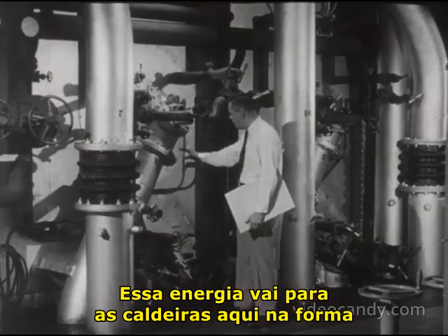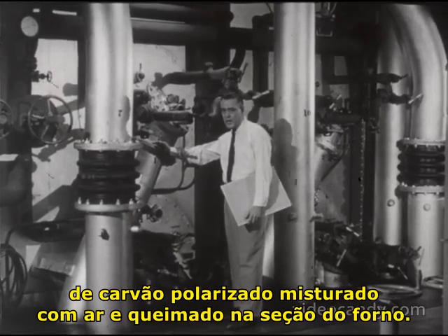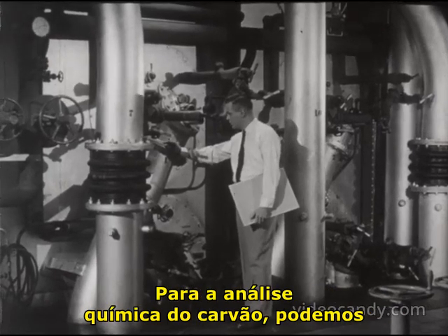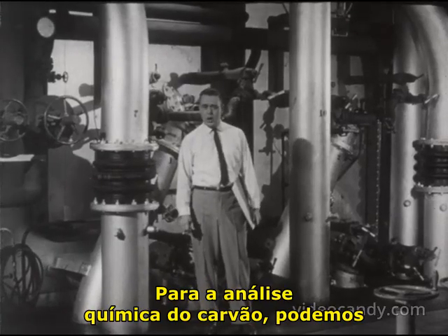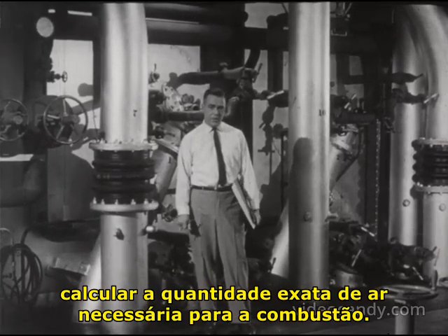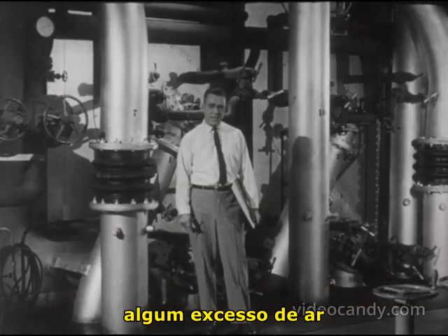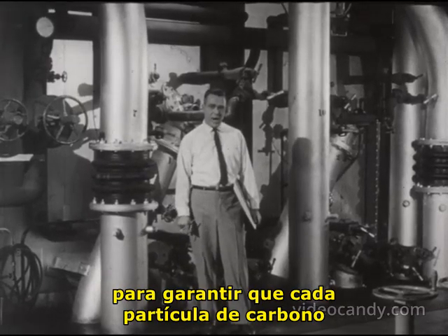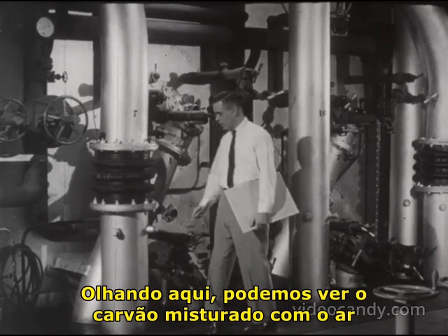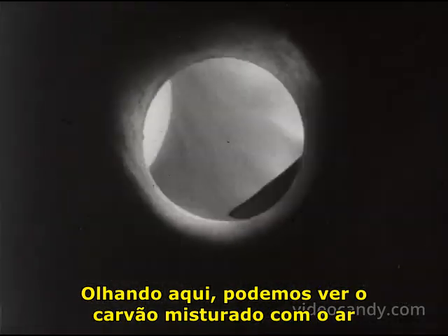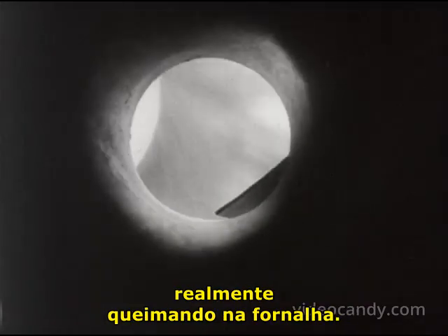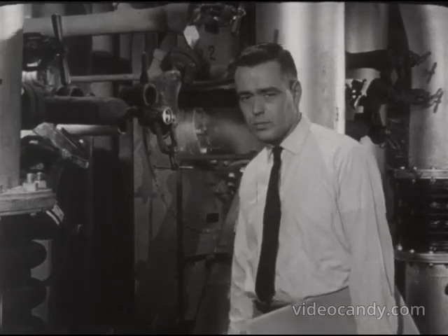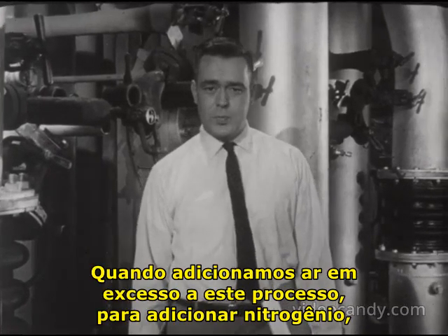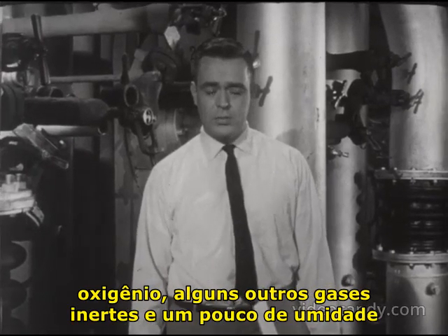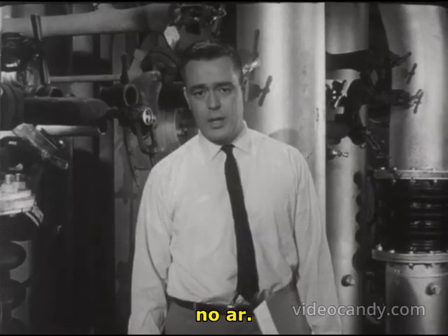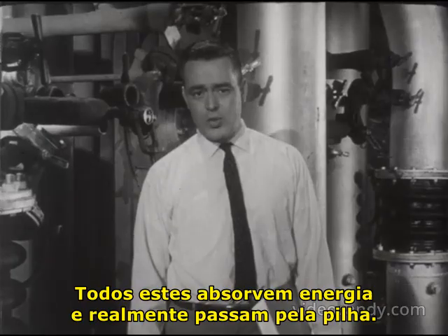Energy is going into the boiler here in the form of pulverized coal mixed with air and burned in the furnace section. With the chemical analysis of the coal, we can calculate the exact amount of air required for combustion. But experience has shown us that we need to add some excess air in order to ensure that each particle of carbon will come into contact with oxygen. Looking in here, we can see the coal mixed with the air actually burning in the furnace. When we add excess air to this process, we're adding nitrogen, oxygen, some other inert gases, and some moisture in the air. All of these absorb energy and actually pass up the stack.